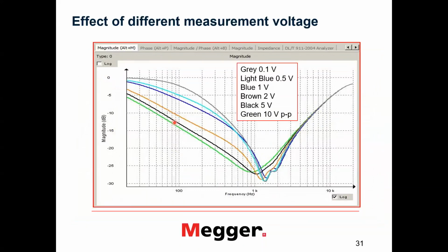Regarding voltage influence, here are some graphs made on the same transformer, just changing voltages from 0.1 to 10 volts peak to peak. And we see that the higher the voltage, the more attenuation we observe in the transformer, and also a little bit different shape of it. So in this case, it is also important to make sure that the voltage level at the test location is the same as in the reference measurement. For example, if the reference measurement is made at 2.8 volts or something similar, then with the FRAX doing measurement at 10 volts, we will not get exactly the reference curve, even if there are no changes in the transformer. So we would have to go back to, say, 2.8 volts.